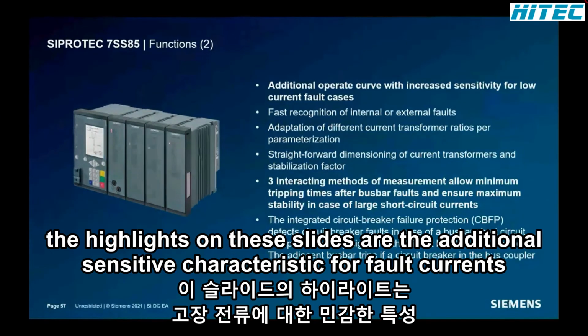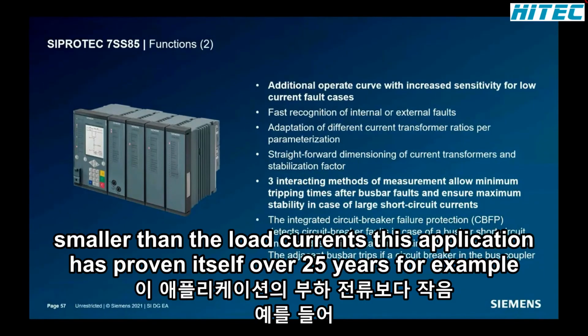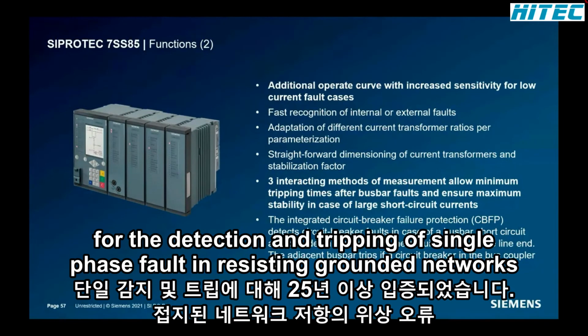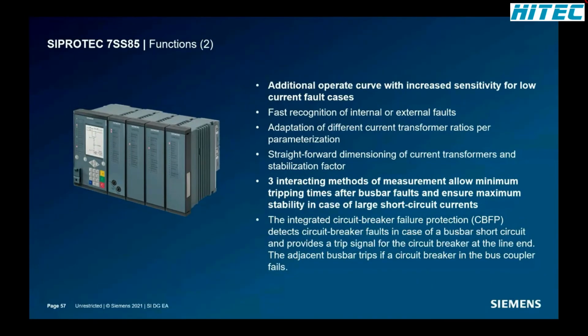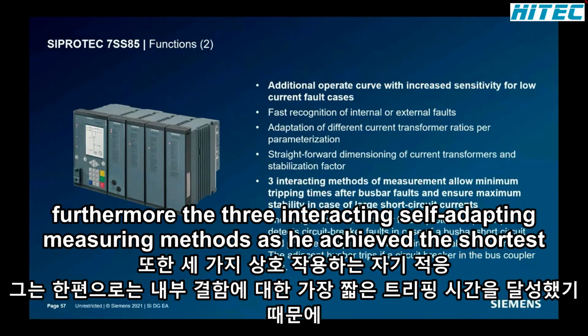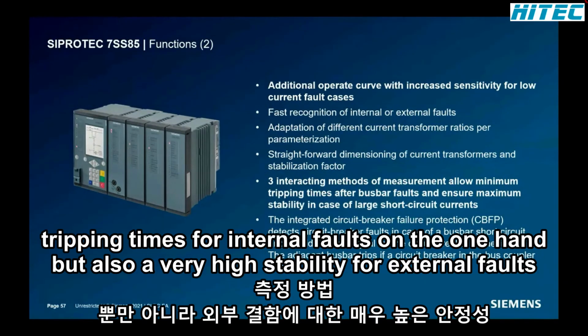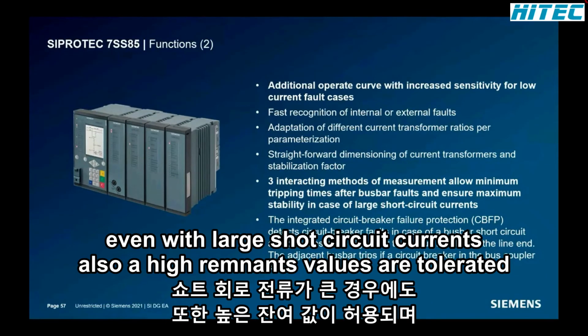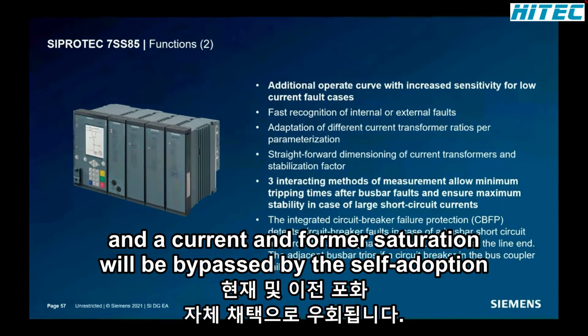The highlights on these slides are the additional sensitive characteristic for fault currents smaller than the load currents. This application has proven itself over 25 years, for example, for the detection and tripping of single-phase faults in resistance grounded networks. Furthermore, the 3 interacting self-adapting measuring methods achieve the shortest tripping times for internal faults on the one hand, but also a very high stability for external faults, even with large short circuit currents. Also, high remanence values are tolerated, and a current transformer saturation will be bypassed by the self-adaptation.